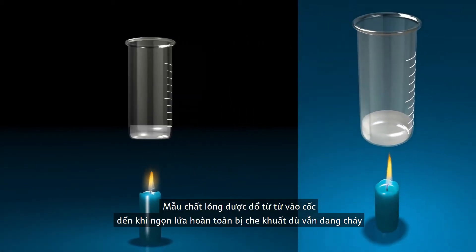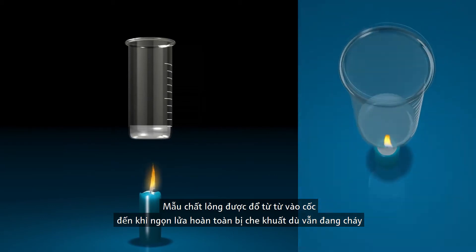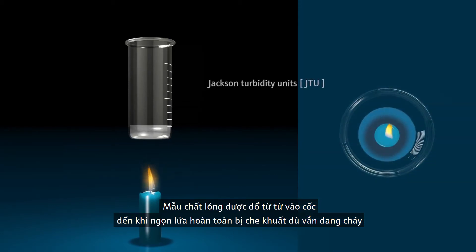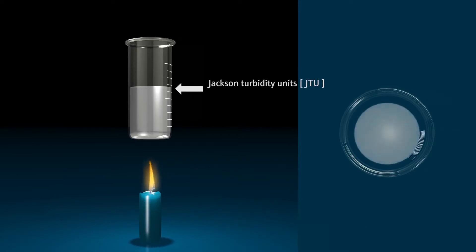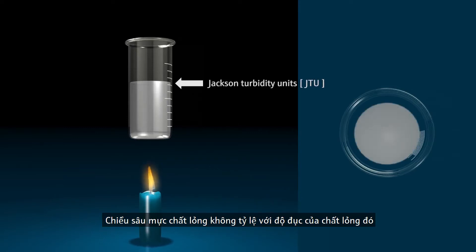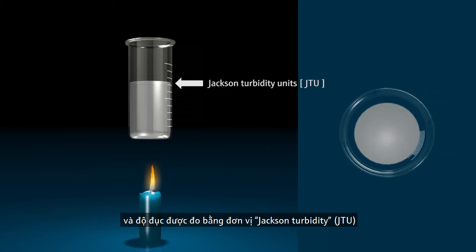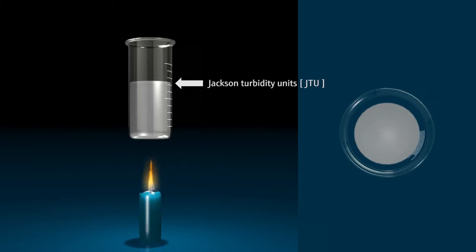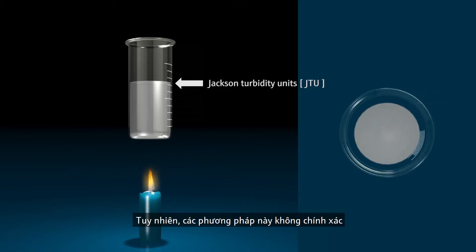A sample is slowly poured into the vessel until the candle flame is completely obscured and changes into an even shine. The sample depth is then related to the silica scale, and the turbidity is measured in Jackson Turbidity Units. These methods are however not precise and depend on the subjective impression of the testing person.